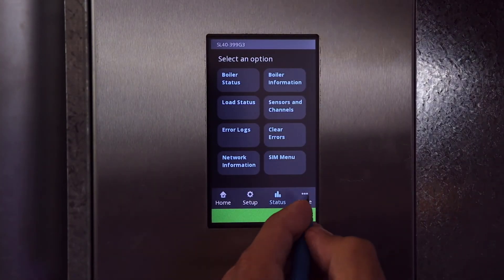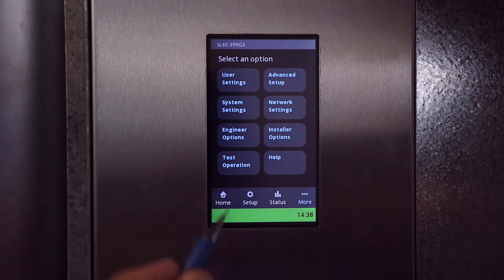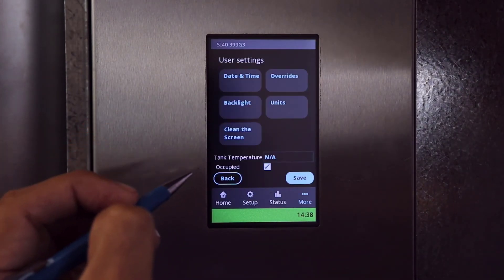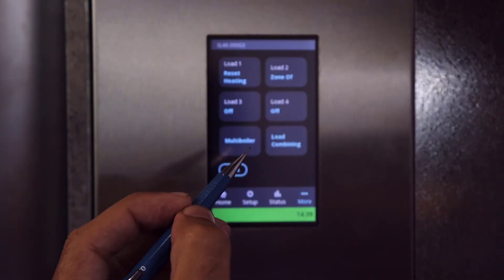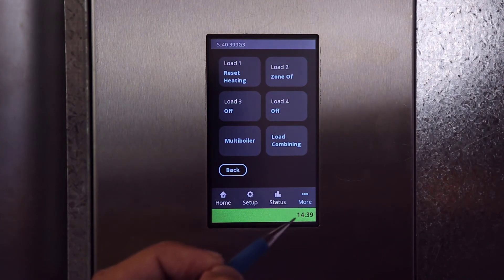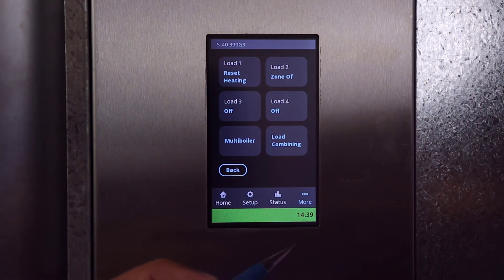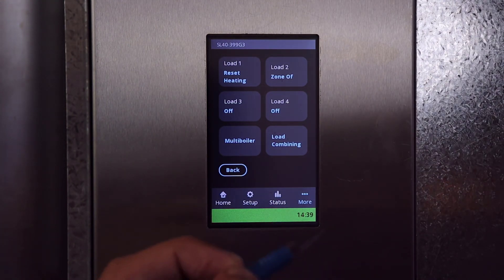Finally, we get to the More tab. Under User Settings you can adjust the time, date, unit settings such as Celsius or Fahrenheit, and find an override schedule. Advanced Setup is comparable to Installer Settings on previous versions. This is where you can enable and edit advanced load parameters not available on the Setup tab, such as ramp speeds, DHW tank differential, combining two loads to run at the same time, and configuring multi-boiler applications.